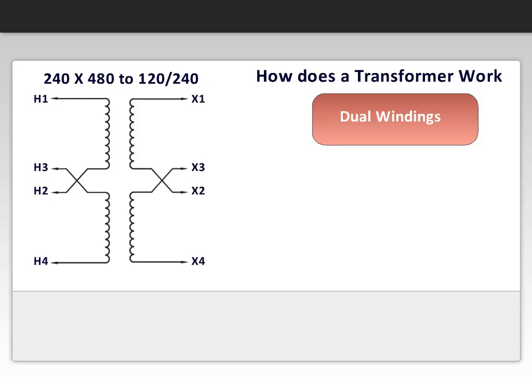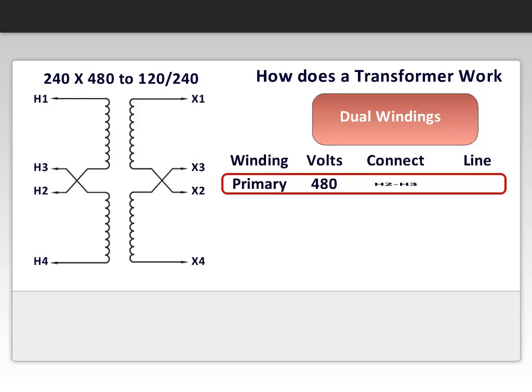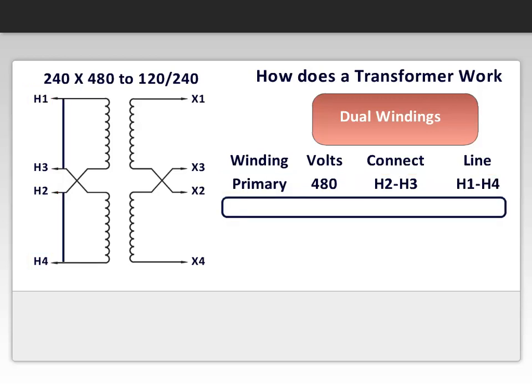Here's how. If the source voltage is 480, then H2 and H3 can be jumpered, and the line can be connected to H1 and H4. If 240 volts, then H1 and H3 are jumpered, and H2 and H4 are also jumpered, and the line is again connected to H1 and H4.